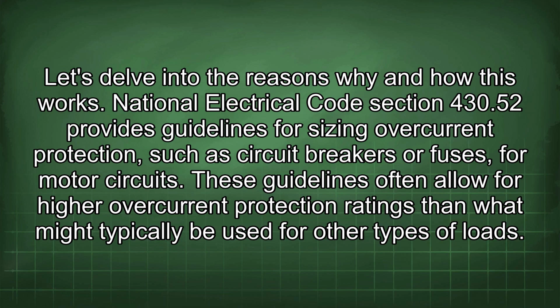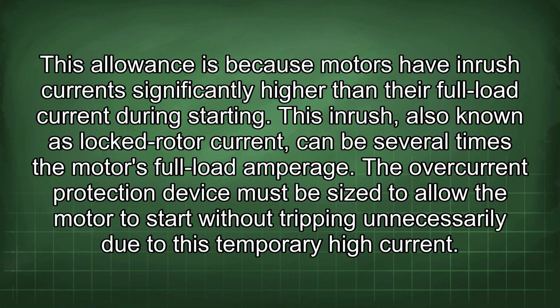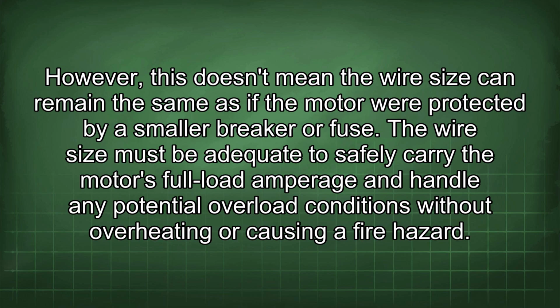National Electrical Code Section 430.52 provides guidelines for sizing overcurrent protection, such as circuit breakers or fuses, for motor circuits. These guidelines often allow for higher overcurrent protection ratings than what might typically be used for other types of loads. This allowance is because motors have inrush currents significantly higher than their full load current during starting. This inrush, also known as locked rotor current, can be several times the motor's full load amperage. The overcurrent protection device must be sized to allow the motor to start without tripping unnecessarily due to this temporary high current. However, this doesn't mean the wire size can remain the same as if the motor were protected by a smaller breaker or fuse.